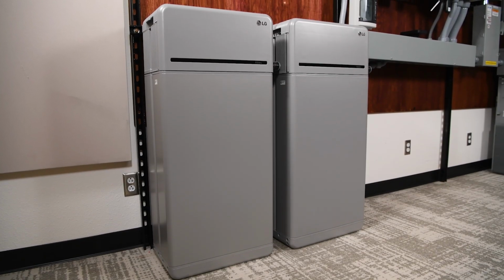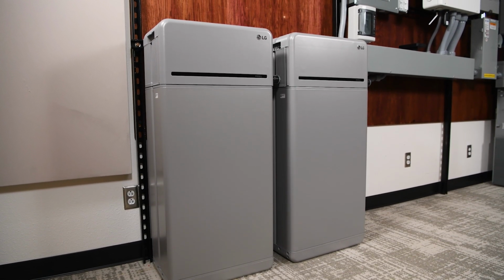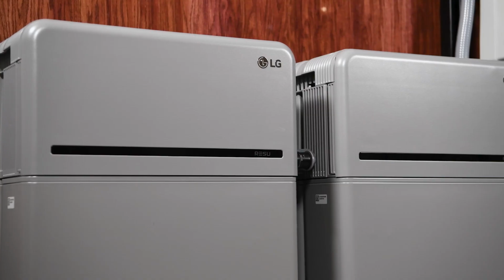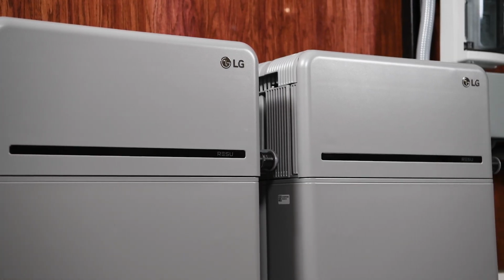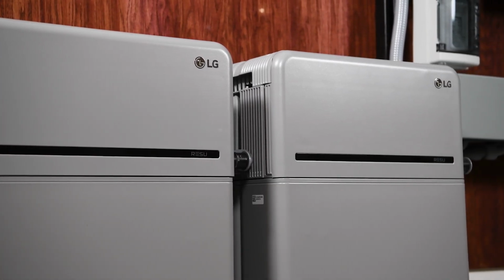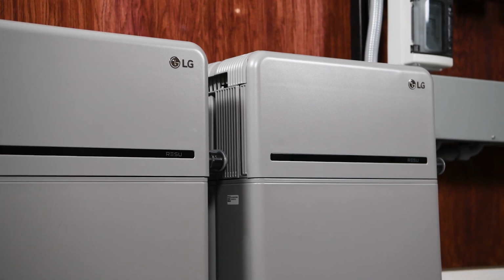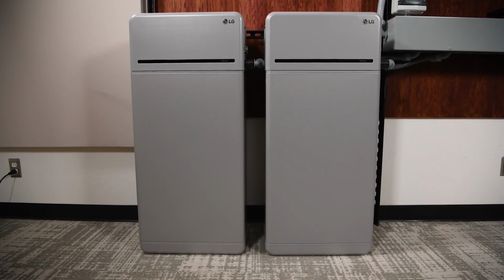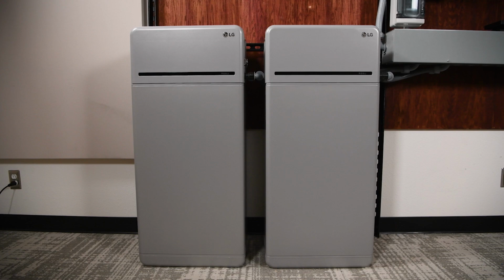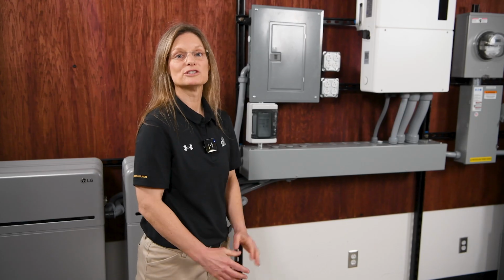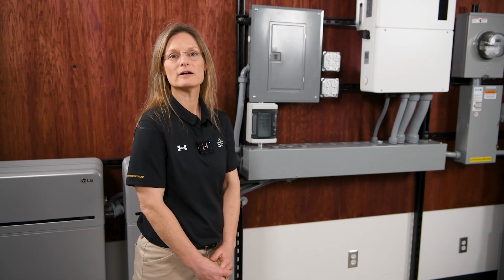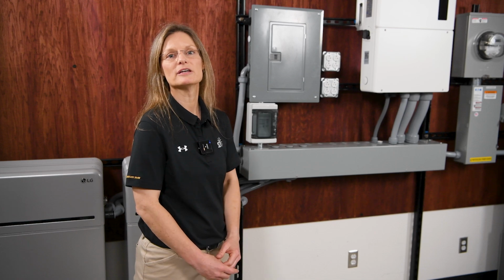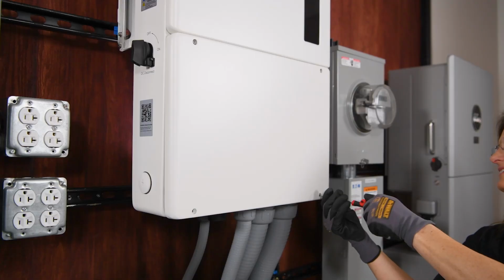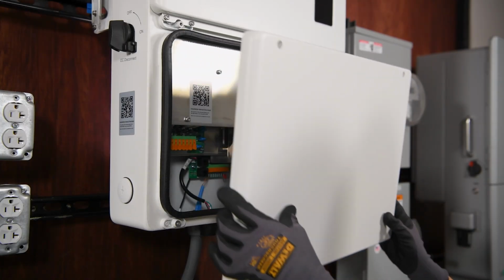The other part of our energy storage system are LG 16H Prime batteries. They can output 7,000 watts continuous power. We can parallel up to 2 of these high voltage batteries, and together they can output 14,000 watts of continuous power. So as you can see, we've already assembled our batteries, we have mounted our inverter, and we've installed our conduit. Now it's time to start wiring up our inverter.